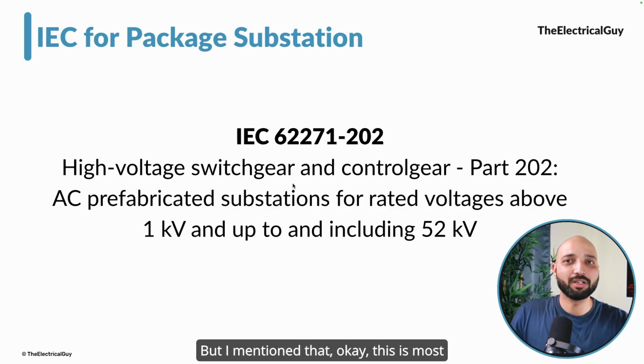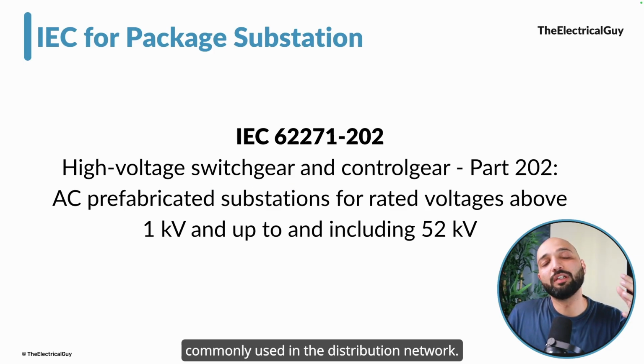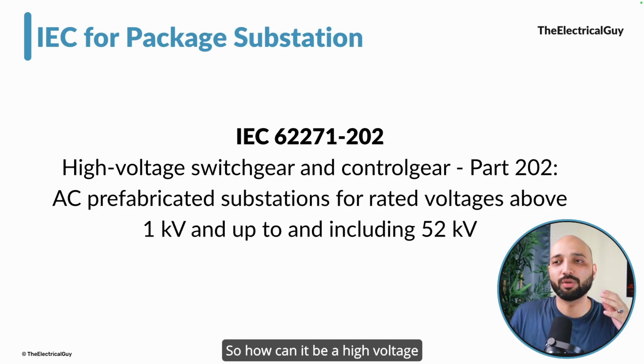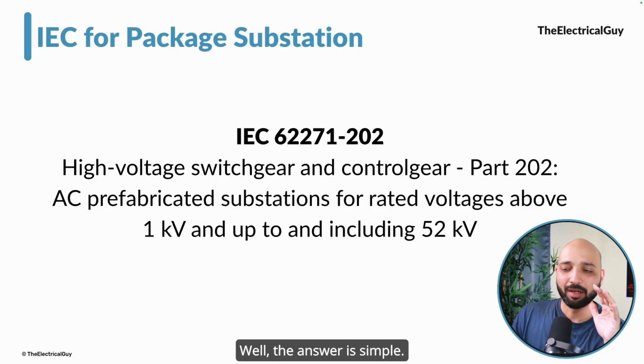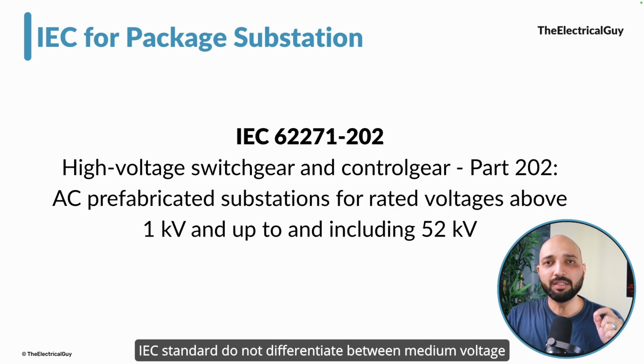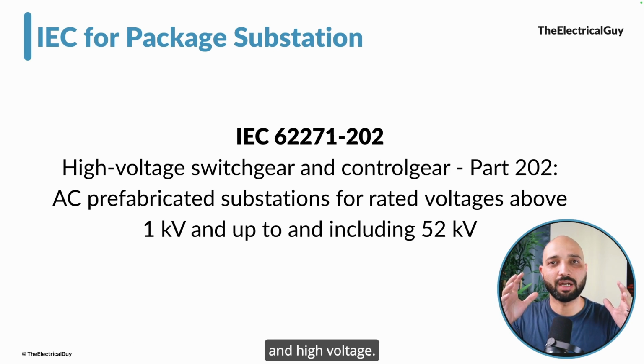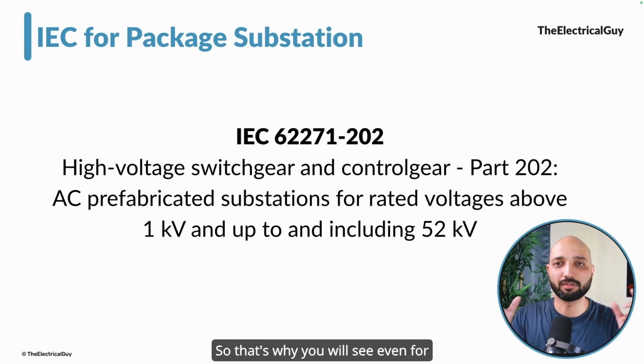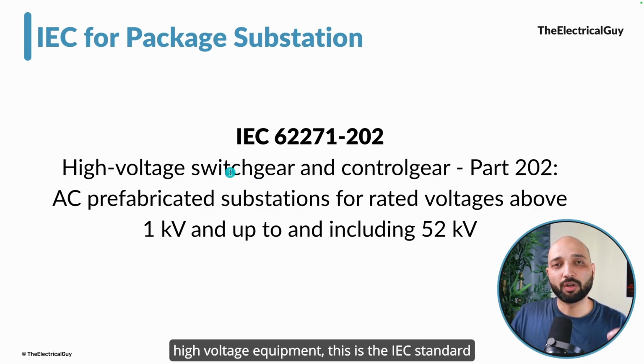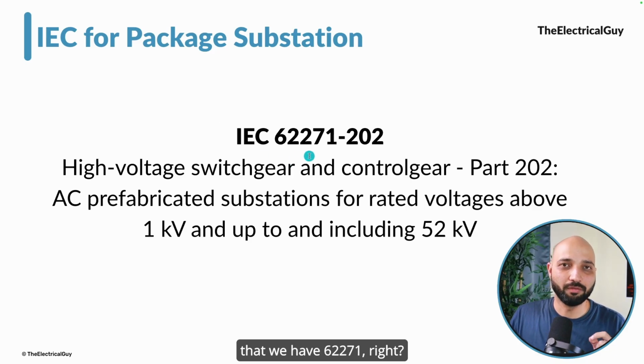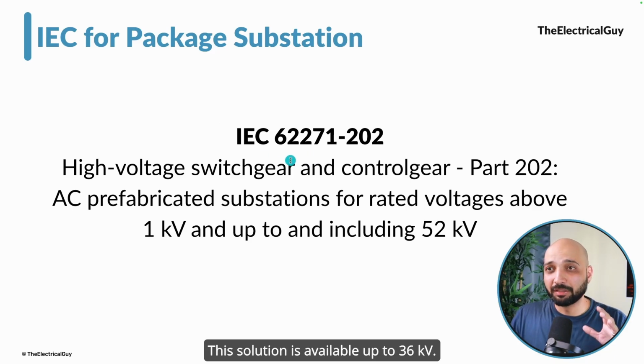But I mentioned that this is most commonly used in the distribution network, so how can it be a high voltage switchgear? Well, the answer is simple: IEC standards do not differentiate between medium voltage and high voltage. So that's why even for high voltage equipment, you will see this same IEC standard, 62271. This solution is available up to 36 kV.